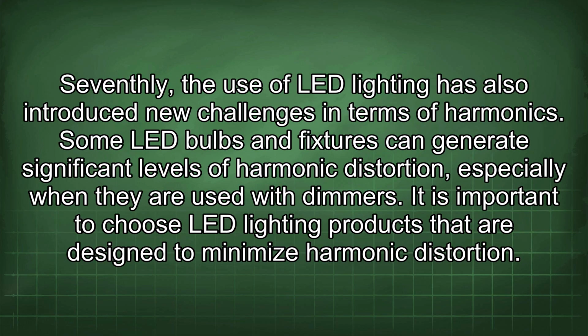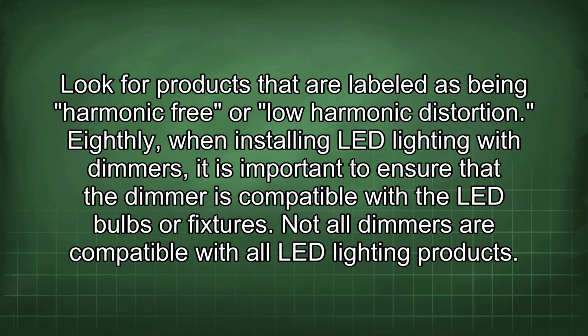Seventhly, the use of LED lighting has also introduced new challenges in terms of harmonics. Some LED bulbs and fixtures can generate significant levels of harmonic distortion, especially when they are used with dimmers. It is important to choose LED lighting products that are designed to minimize harmonic distortion. Look for products that are labeled as being harmonic-free or low harmonic distortion.